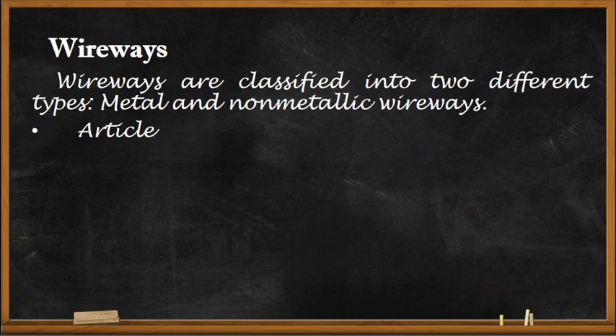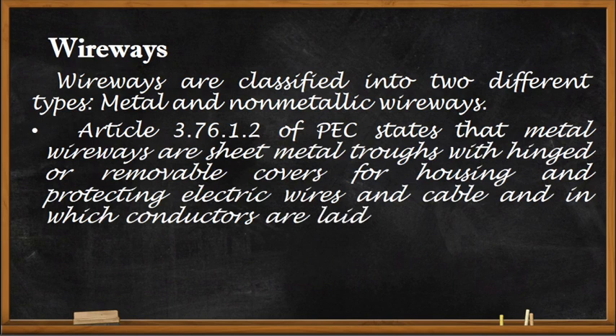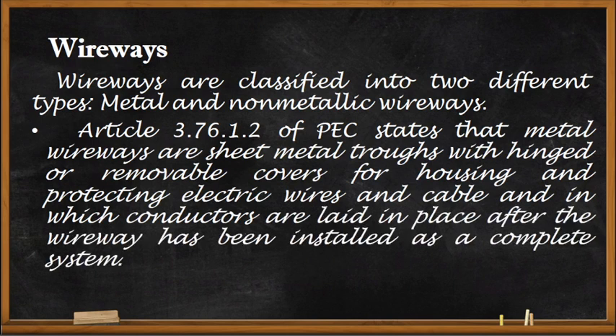Wireways are classified into two types: metal and non-metallic. Article 3.76.1.2 of the Philippine Electrical Code states that metal wireways are sheet metal troughs with hinged or removable covers for housing and protecting electric wires and cables, in which conductors are laid in place after the wireway has been installed as a complete system.